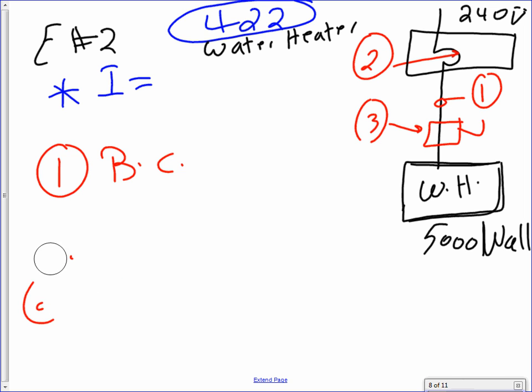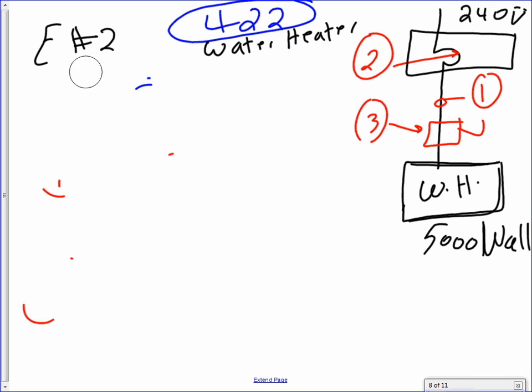And I need to size, like I said, the following. Example number 2 is a water heater, and we need to size a few things for this water heater. It's a 5,000 watt, 240 volt water heater. We need the conductor, the disconnect, and the overcurrent protection device. 3 things only. Not a whole lot. Okay, let me know when you guys are ready to go.